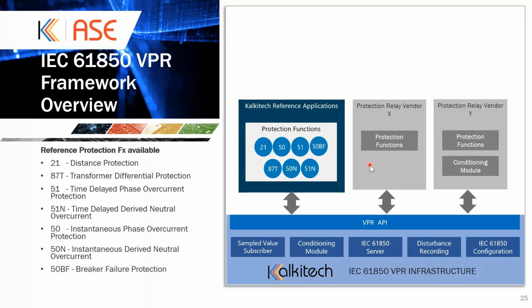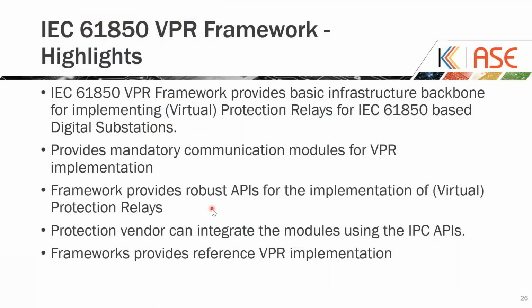So we used this VPR framework for creating the VPR reference application. Highlights of the VPR framework are that it has a basic framework that can be used as a backbone for implementing protection relays and different IEC 61850 tools. It has many mandatory communication modules as per the IEC 61850 standard, and it has very robust APIs that can be implemented and integrated with the protection algorithms.